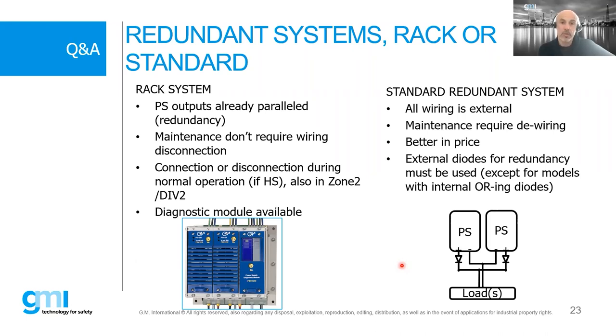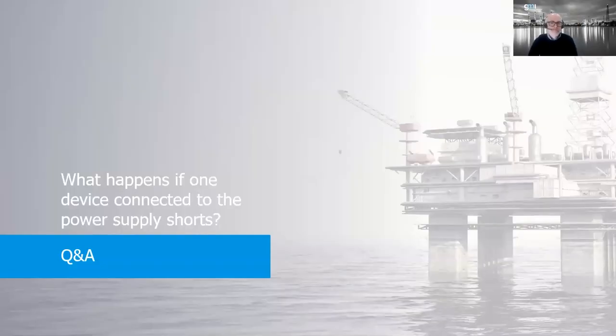You don't need to disconnect the wiring in case of maintenance. It can also be mounted in zone 2 and hot swapping, and there is also this diagnostic. But basically, the wiring is made in the factory, so it's made with a rack, so you don't need to wire any external diodes because the diodes are already inside the modules. While in a standard power supply, you need this external kit to make the redundancy.